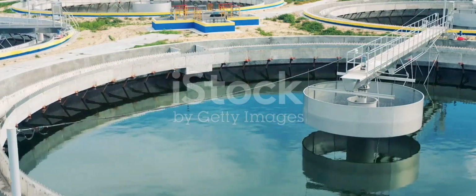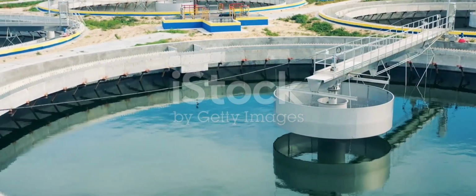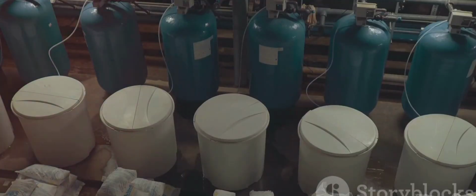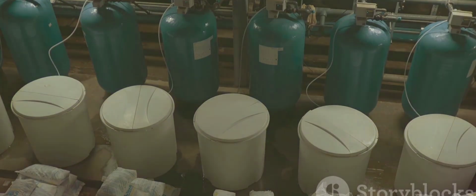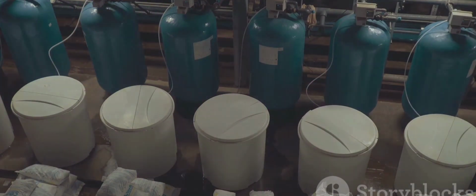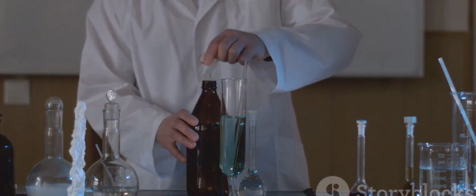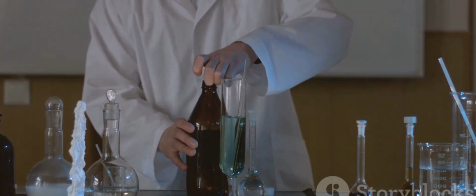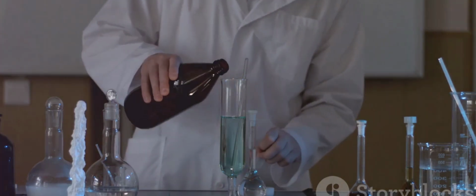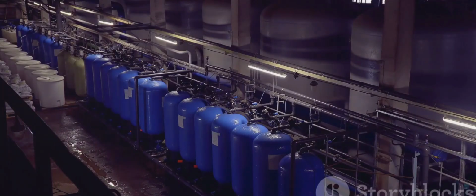Water softening or deionization, if required. In industries where water hardness affects equipment performance, water softening, which is an ion exchange process, or deionization may be necessary to remove calcium, magnesium, and other ions that cause scaling. Key parameters include total hardness, which is measured in milligrams per liter or grains per gallon, ion exchange capacity, measured in milliequivalents per liter, and the regeneration cycle frequency.